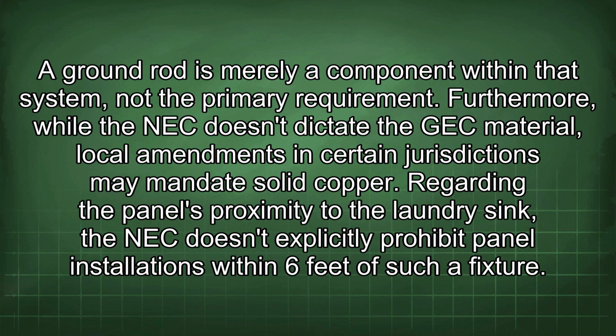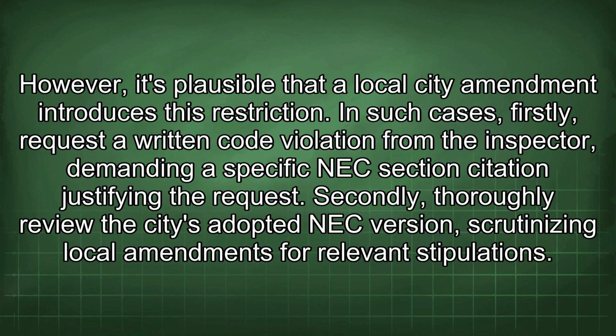Furthermore, while the NEC doesn't dictate the GEC material, local amendments in certain jurisdictions may mandate solid copper. Regarding the panel's proximity to the laundry sink, the NEC doesn't explicitly prohibit panel installations within 6 feet of such a fixture. However, it's plausible that a local city amendment introduces this restriction.